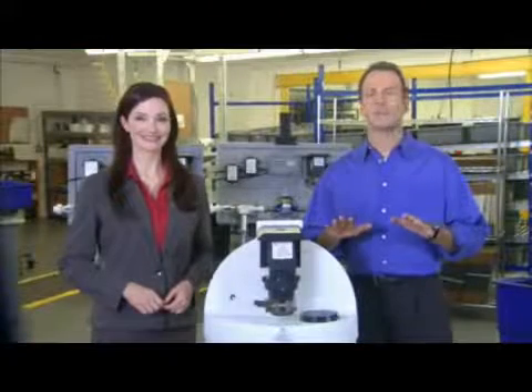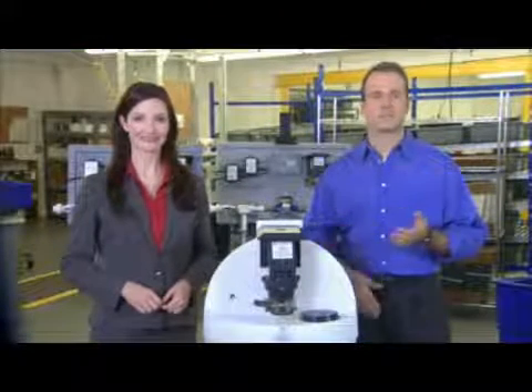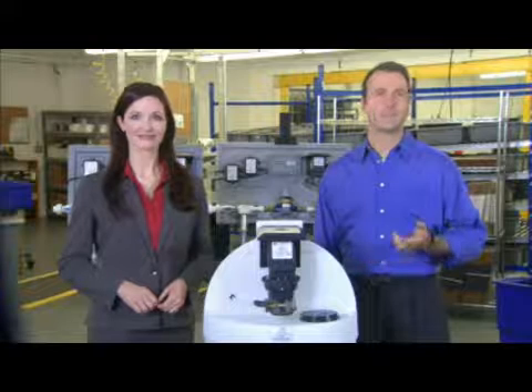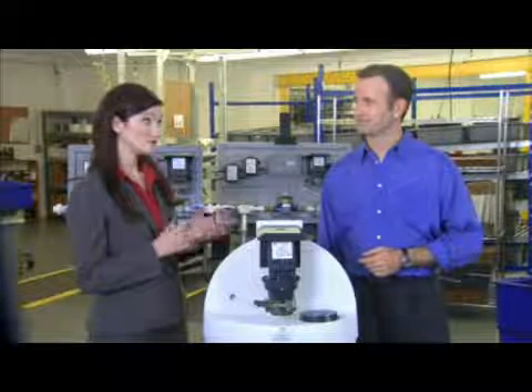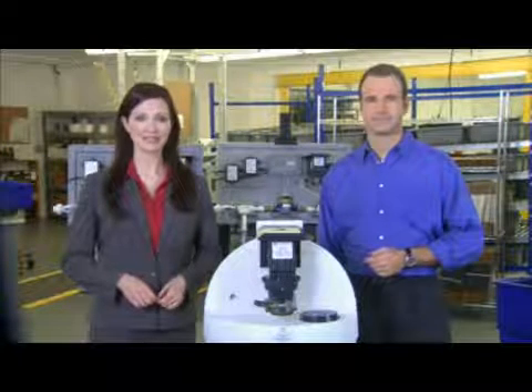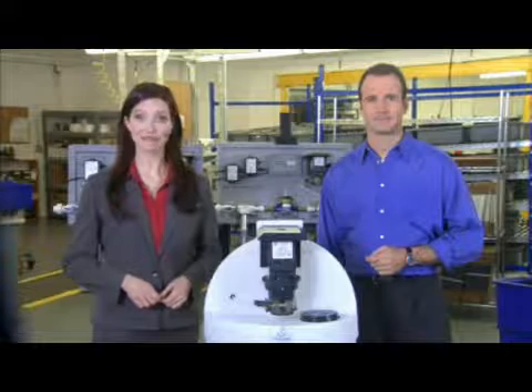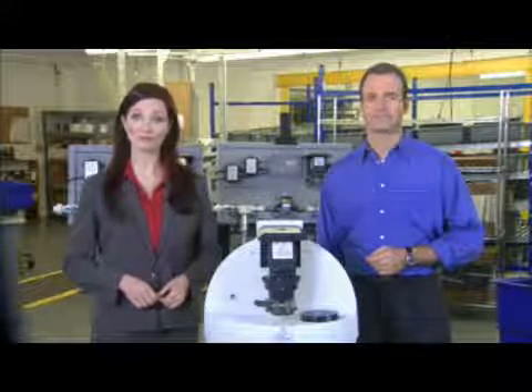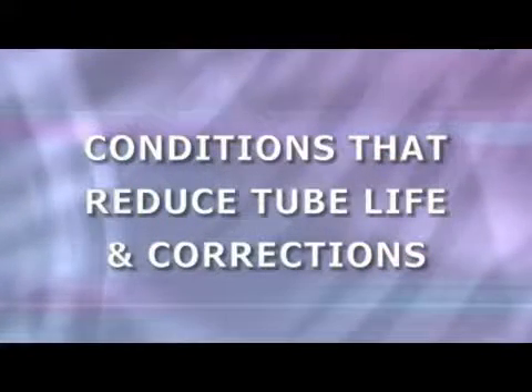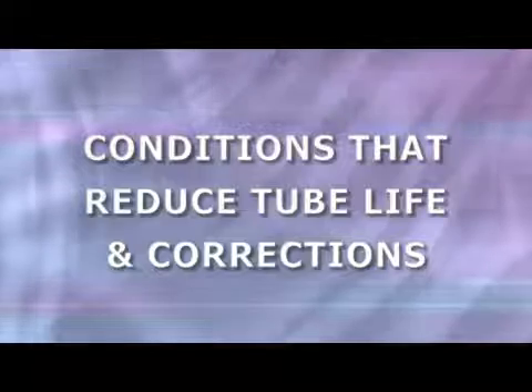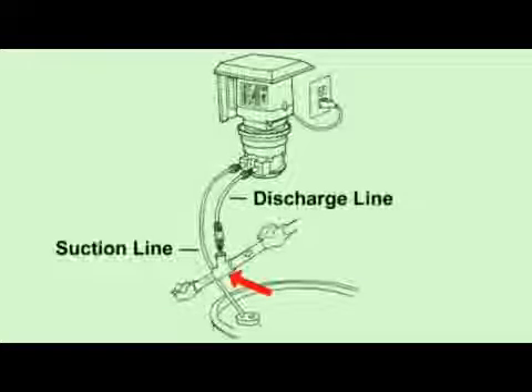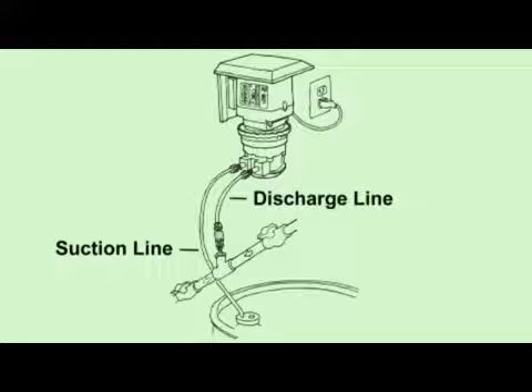We've seen that following the factory installation points helps protect the life of the tube, the pump, and quite simply your investment. And to further protect your investment, it's good to know some of the conditions that can contribute to reducing the life of the pump tube. Excessive back pressure at the point of injection can damage the pump tube. The excessive pressure can be created from the suction or discharge side due to blockage.